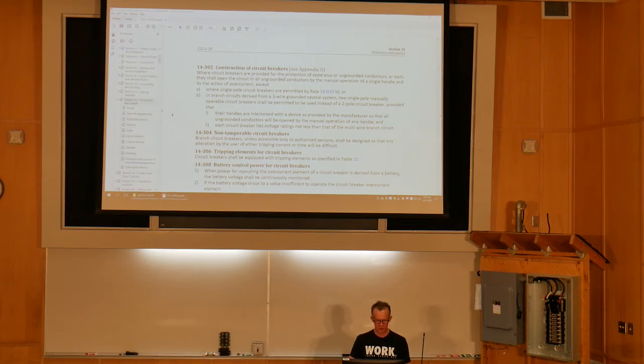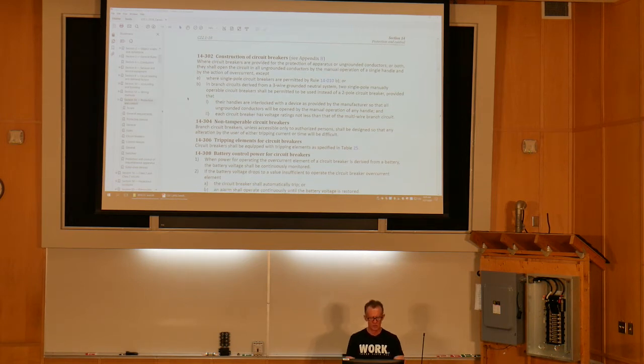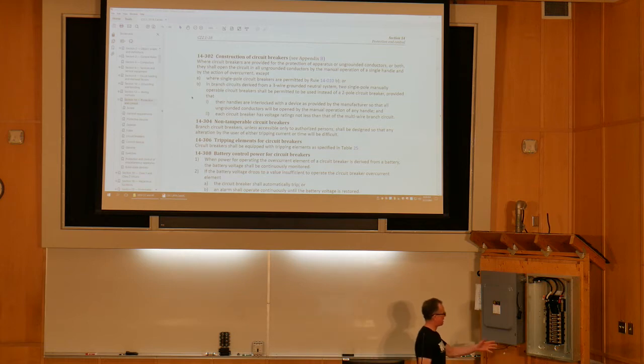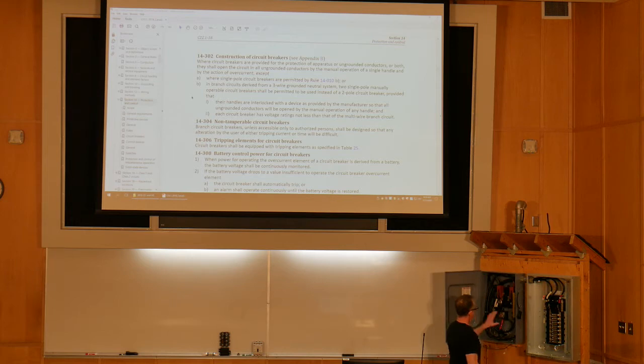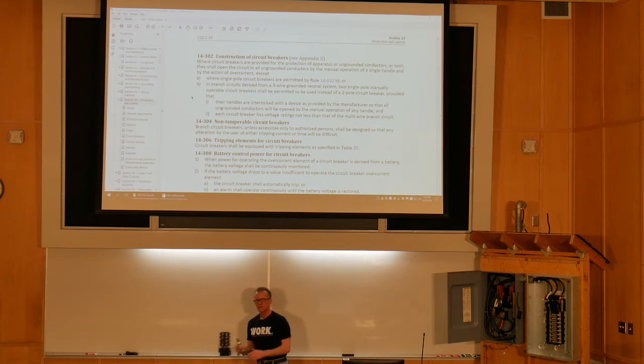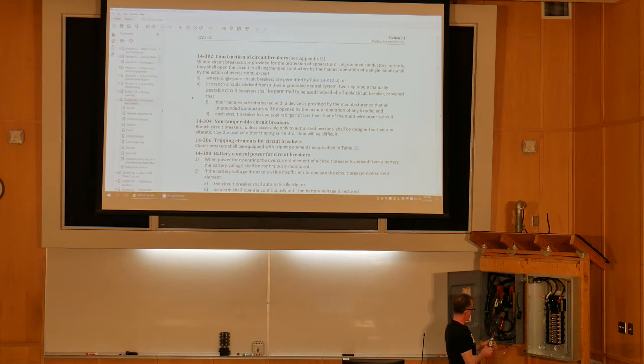Construction of circuit breakers, 14-302. Where circuit breakers are provided for the protection of apparatus or ungrounded conductors. So apparatus, protection. These fuses in here protect this apparatus, this panel board. The branch circuit breakers here would protect the branch circuit conductors and whatever equipment is connected to them. So these fuses, this cartridge fuse, and this switch in here protect these conductors and this apparatus.